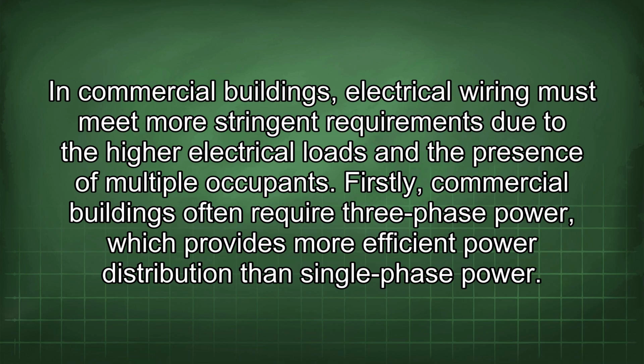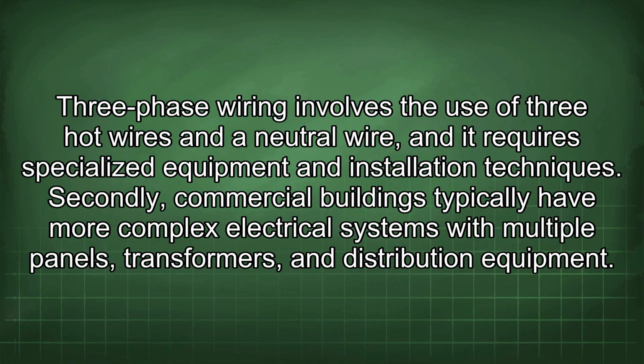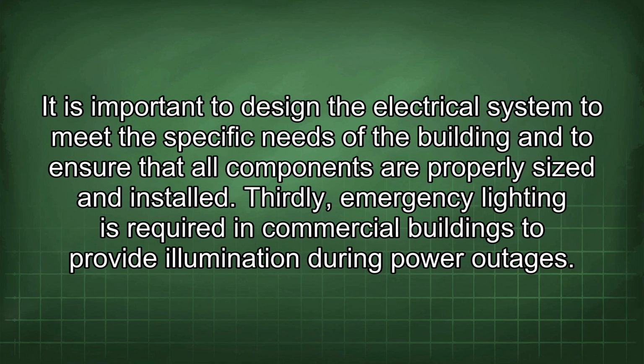presence of multiple occupants. Firstly, commercial buildings often require three-phase power, which provides more efficient power distribution than single-phase power. Three-phase wiring involves the use of 3 hot wires and a neutral wire, and it requires specialized equipment and installation techniques. Secondly, commercial buildings typically have more complex electrical systems with multiple panels, transformers, and distribution equipment. It is important to design the electrical system to meet the specific needs of the building and to ensure that all components are properly sized and installed.